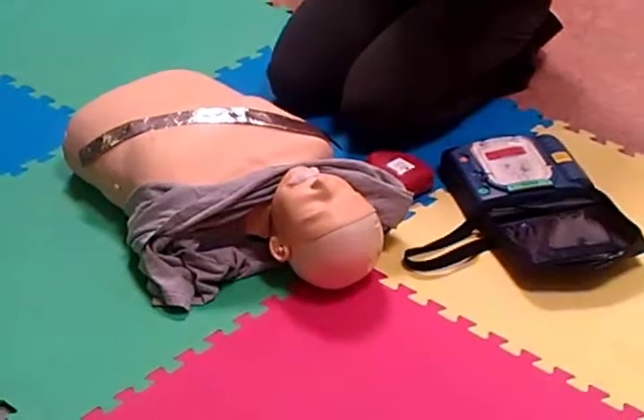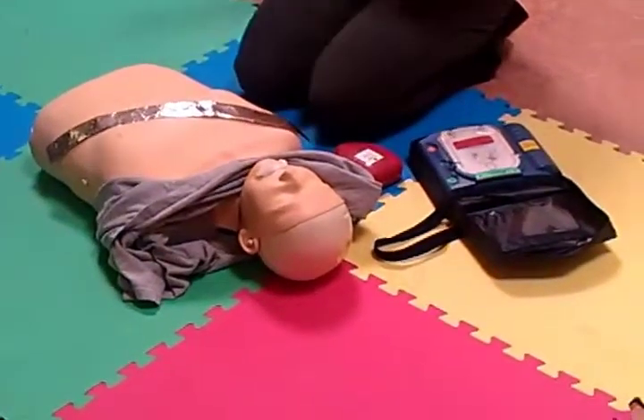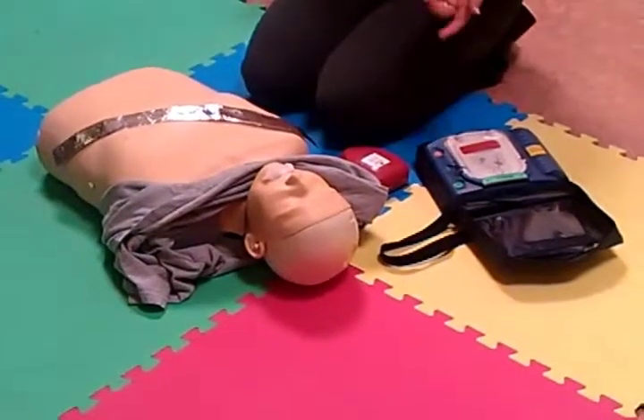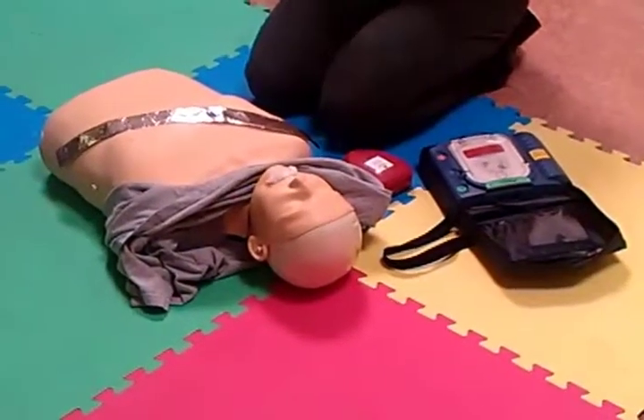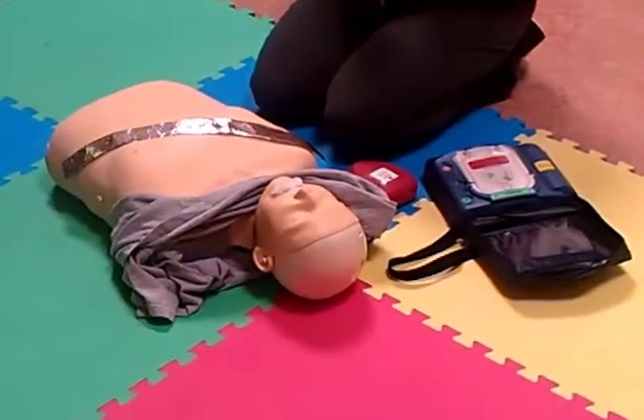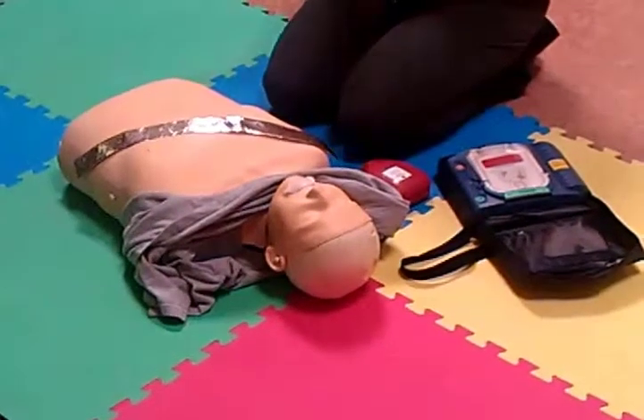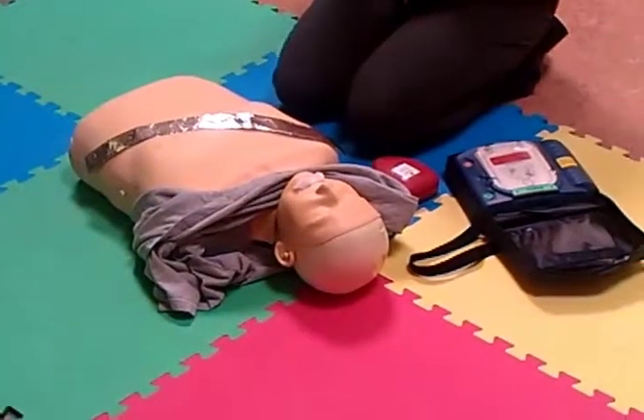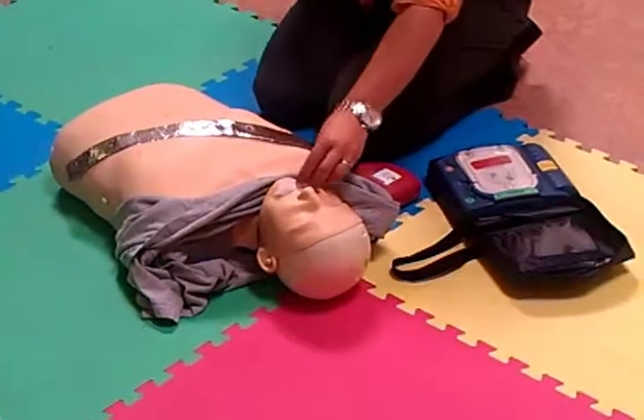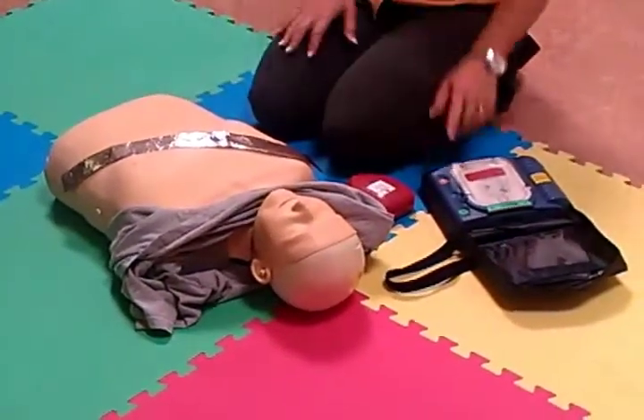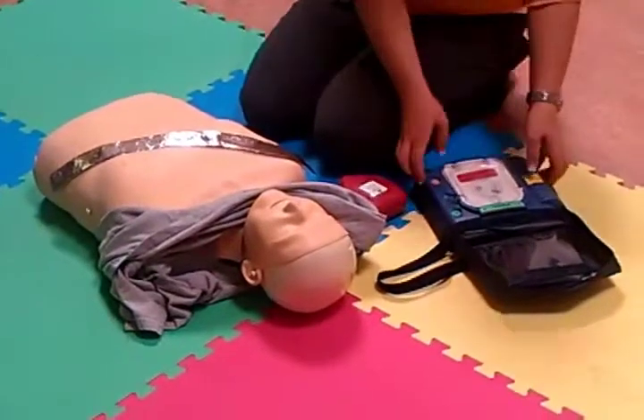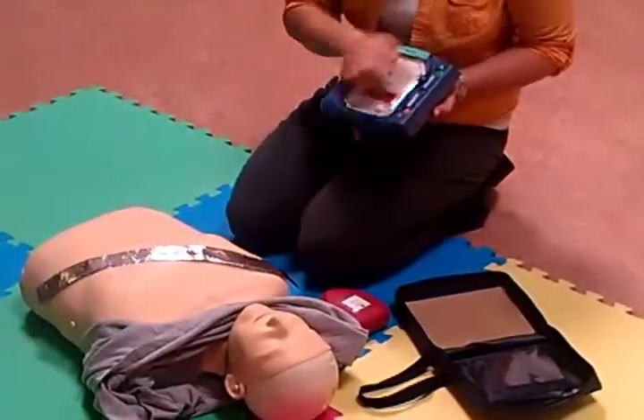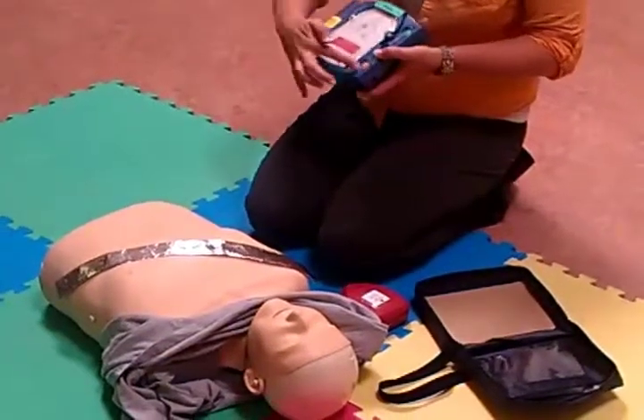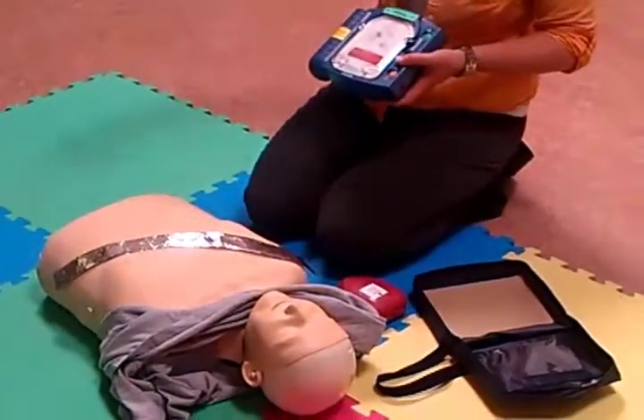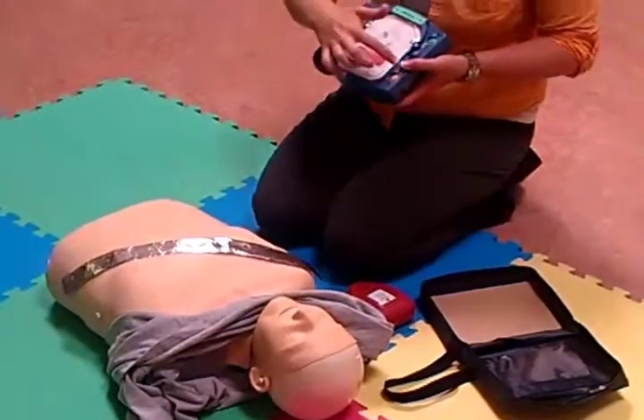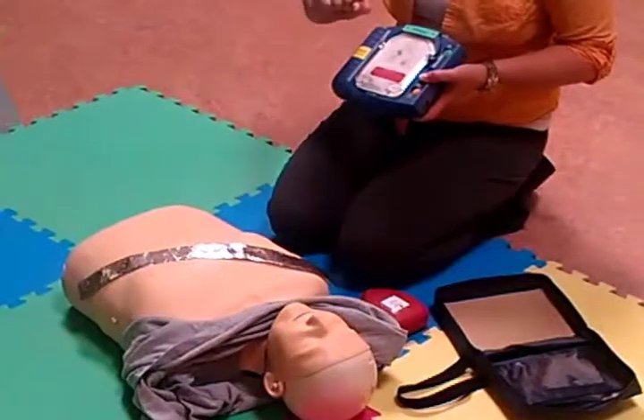And the other thing too is that when the machine is analyzing, it's really important that you stay still because excessive movements around these machines can throw them off as well. Other than that, they are foolproof in that they won't shock a beating heart. What it does is once it's attached to the patient's chest, it'll say analyzing, and then if it picks up a shockable rhythm, it will advise you shock advised. And then to put your finger on the shock button, which is here. So this is the on button, this is the shock button. And we really encourage people to put their finger on the shock button and look around. And then when the machine says deliver the shock, you push the button right away, but still looking around to make sure that no one's touching the patient.